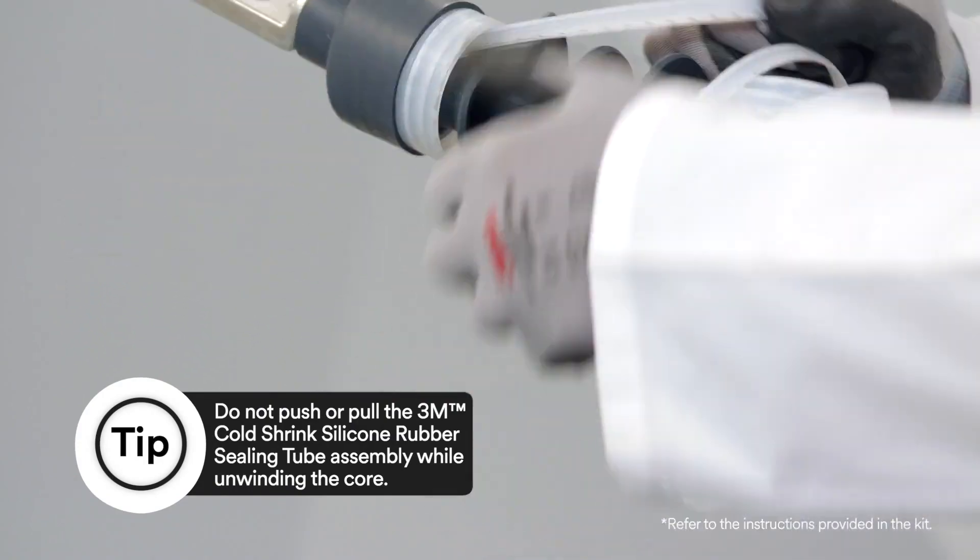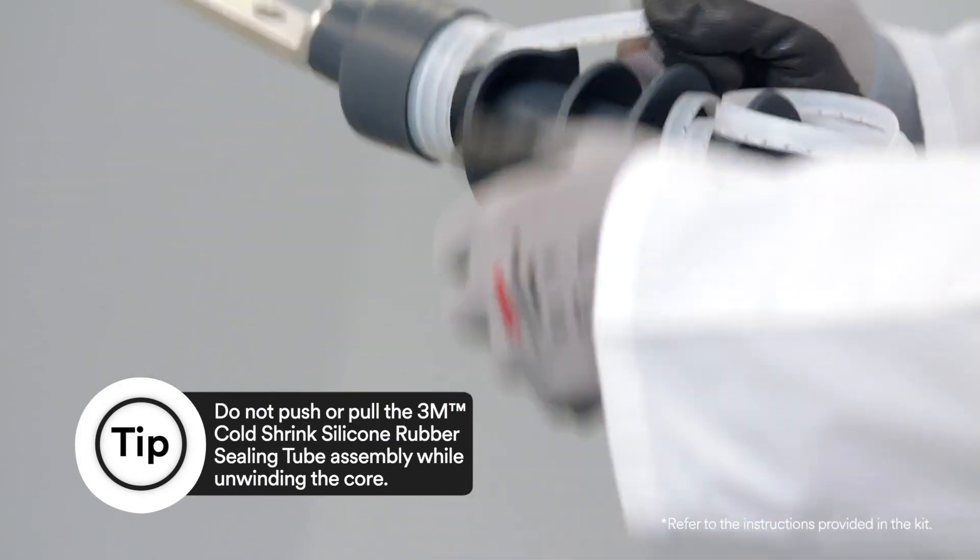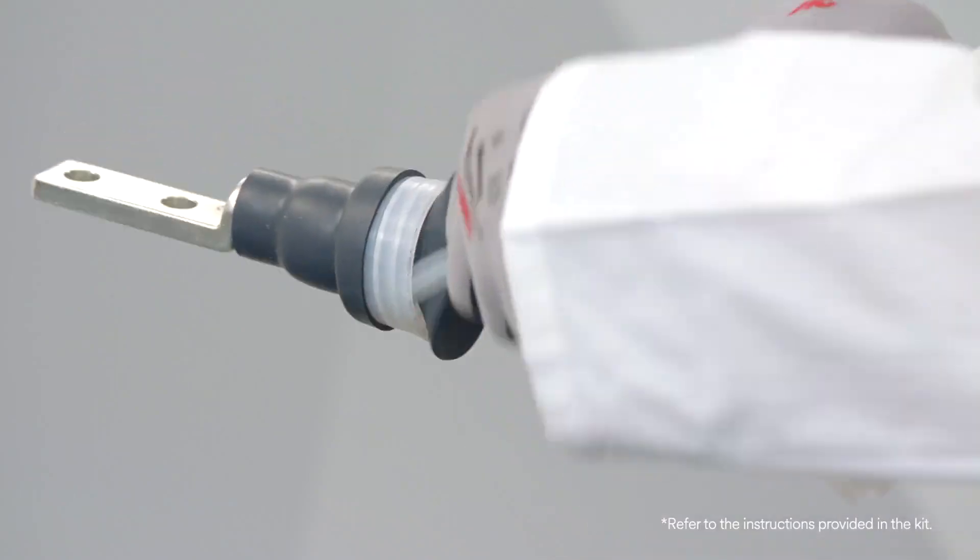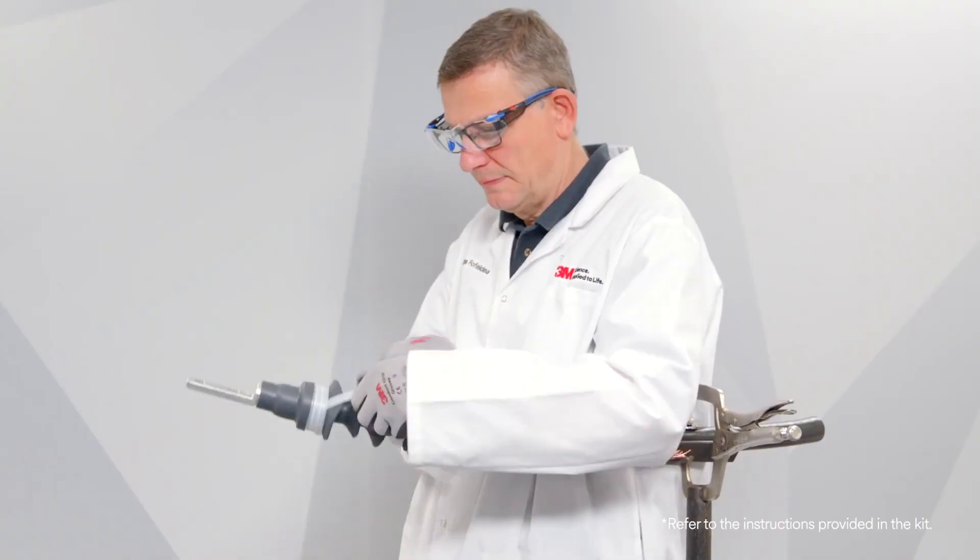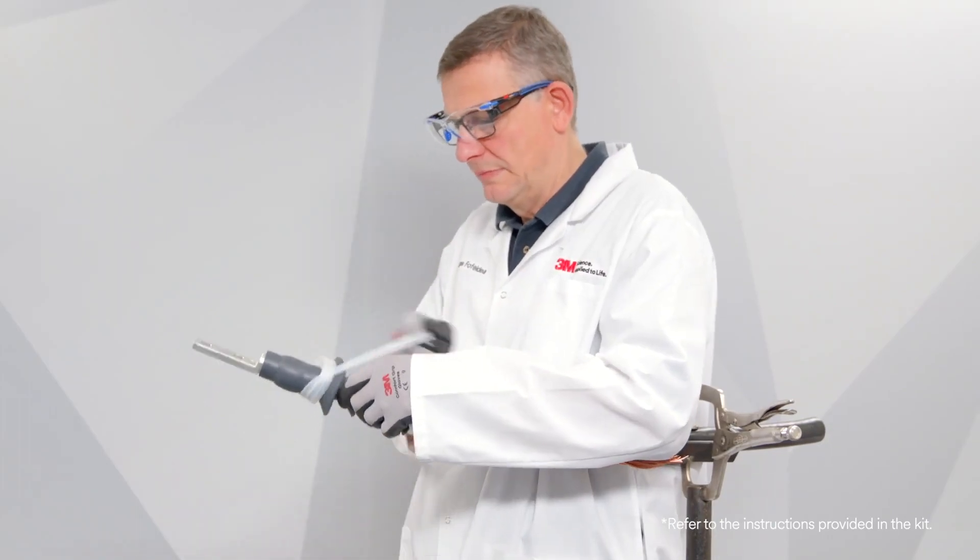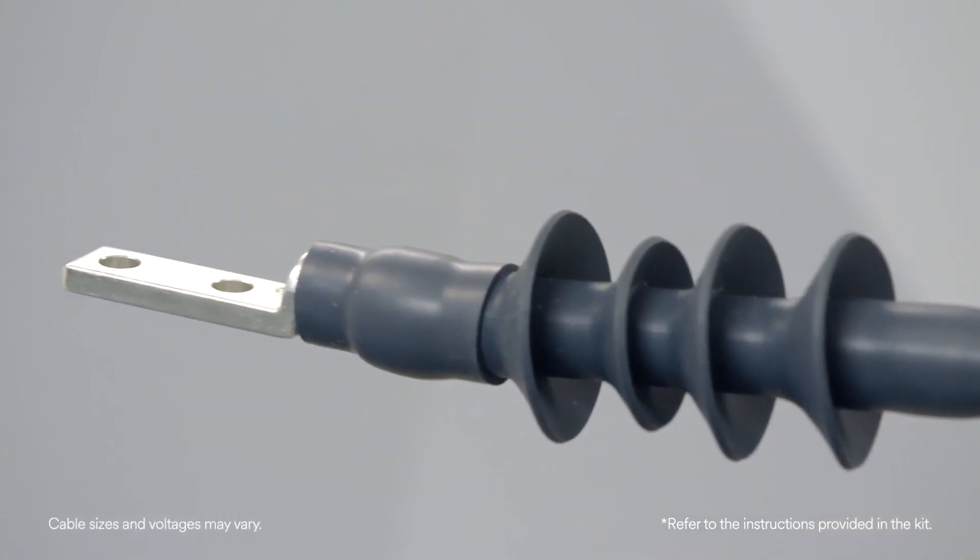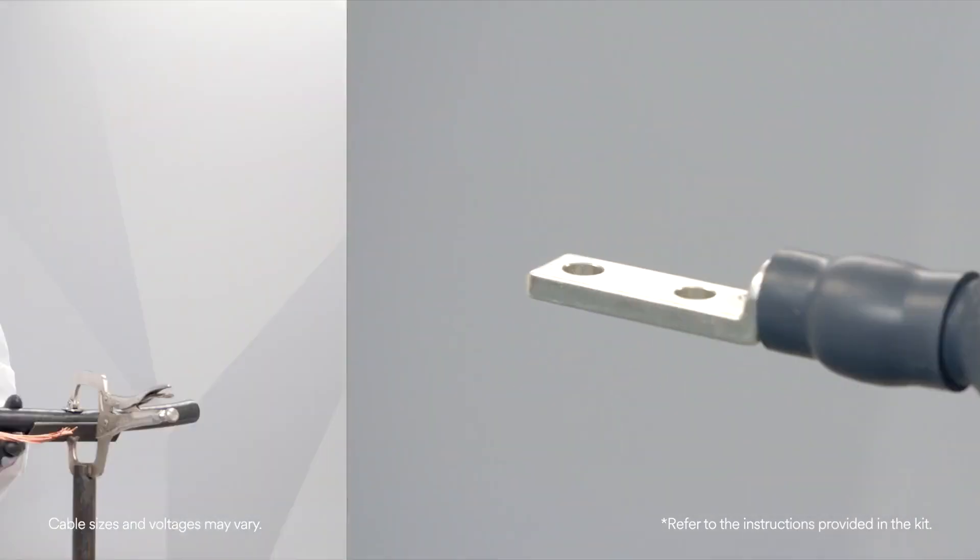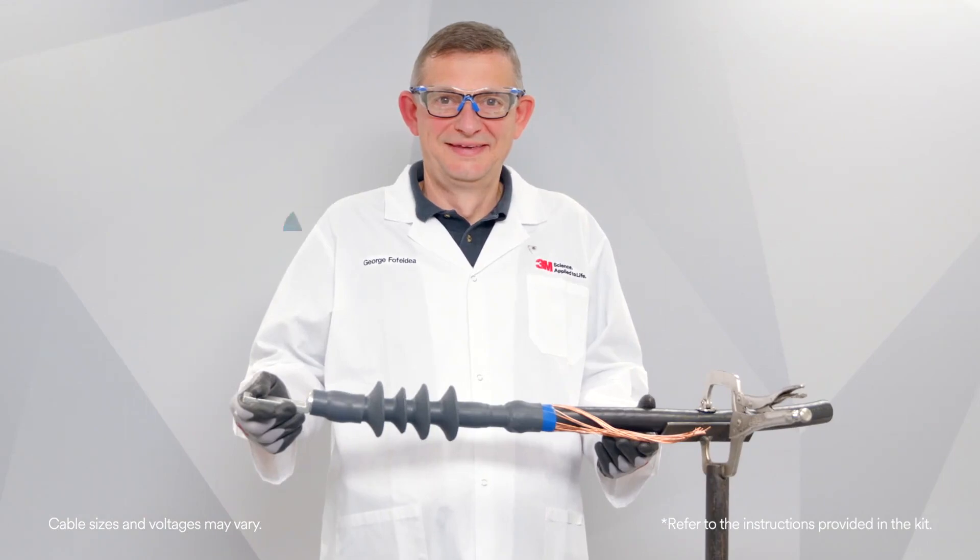Complete the removal of the core by pulling the core ribbon while unwinding counterclockwise. Be sure to alternate pulling and unwinding actions to help prevent the core material from binding up as the core is being removed. And that's how you install a 3M cold shrink QT3 silicone rubber skirted termination.